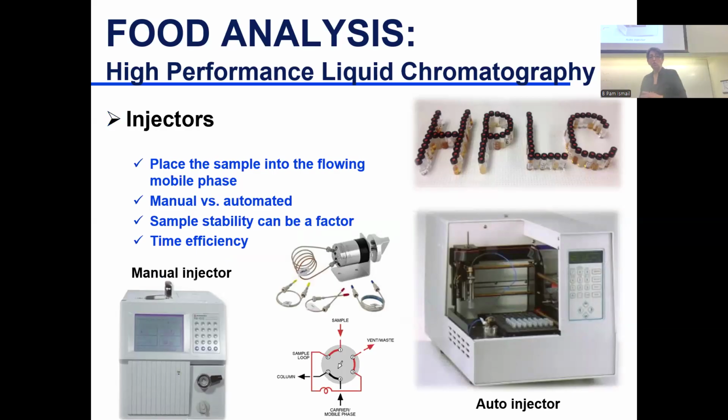Then the injector, you saw in lab, the auto injector, where the needle itself wanders and goes to the tube based on the program, the number of the tube, and goes into the septum, which is the cover you had in that rubber area. It penetrates that rubber, goes in and takes out a selected volume that you have programmed it to. In the case of what we did in the lab, it was 20 microliters.